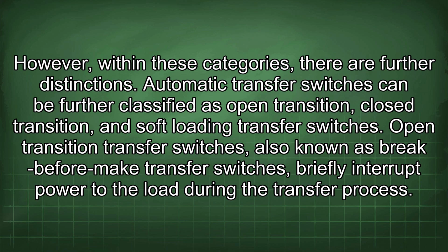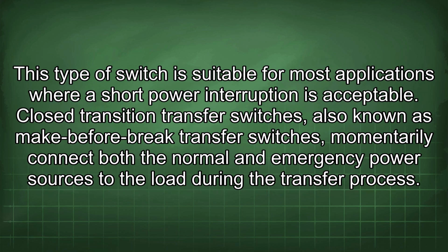Automatic transfer switches can be further classified as open transition, closed transition, and soft loading transfer switches. Open transition transfer switches, also known as break before make transfer switches, briefly interrupt power to the load during the transfer process. This type of switch is suitable for most applications where a short power interruption is acceptable.